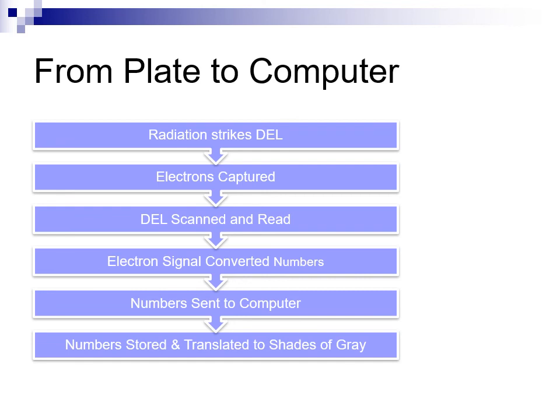To summarize this process, radiation strikes the DEL and causes an electron flow within the DEL proportional to the amount of radiation striking it. The DEL stores these electrons in a capacitor, awaiting to be read by the plate's electronics. Each of the DELs are read and scanned, and the electronic signal is converted into digital numbers. The digital numbers are sent to the computer and stored in memory. Finally, the numbers are copied to screen memory and displayed as an image.